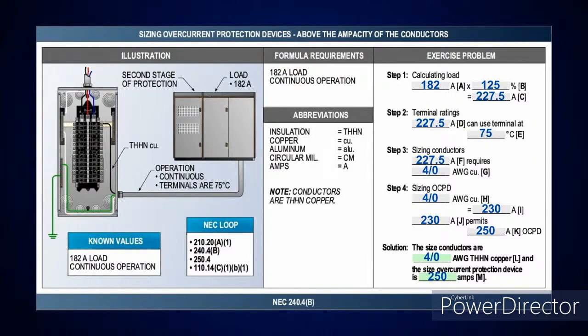Now, look at this. You'll get more. This is 182 amps of continuous load. Now, if it's continuous, what do I take it at? 125%. So that gives me 227.5 amps at 75 degrees C terminals. If I go over in step 3, I look at Table 310.16, the next size above that in the 75 degrees C column, which is a 4-aught, which is good for 230 amps. In this case, I could protect the load or the conductor. I'm looking at 227.5 amps. The next size overcurrent device above that anyway is going to be what?